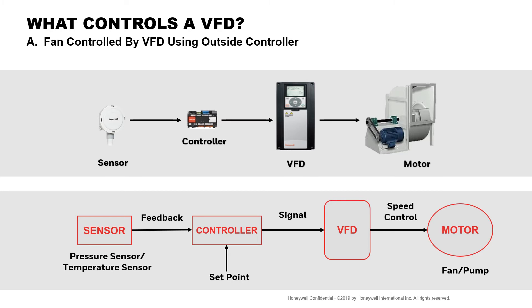VFDs are controlled by sensors — temperature, pressure, or CO2 sensors. The sensor is either wired through a controller or straight to the VFD. In this example, a duct sensor is wired to a DDC controller. The controller is commanding the VFD's speed. Most VFDs operate as part of a DDC system. In these cases, the DDC system provides the smarts.